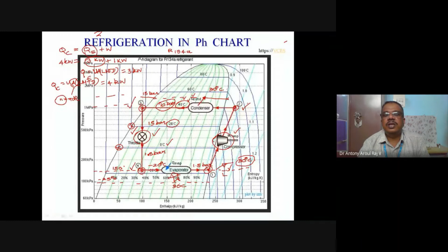Here you can see this is the compressor, and from the compressor, the heat pump is used in the heating mode. In heating mode, the condenser should be indoors. You can see this is indoor, and this is outdoor. From the compressor you get the hot gas, and that hot gas should go to the indoor. Now we have a three-way valve, which is diverting. It closes these two and makes the compressed high-temperature, high-pressure refrigerant vapors go to the indoor, so there you will have heating inside.